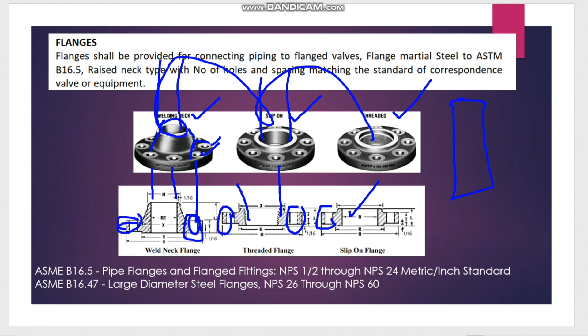So for this flange connection, these holes must match with the mating connection. For example, when you are installing the same flanges with the valves, or the flow meter like you see here, you have to provide flanges to connect with this line also. At that time both the nut and bolt, or the fastener, have to match the flow meter as well as the piping flanges. Coming to flanges, we refer to two important standards. The first one is ASME B16.5. This is for flanges up to 24 inches. Above 26 inch up to 60 inch, we can use the reference standard ASME B16.47.